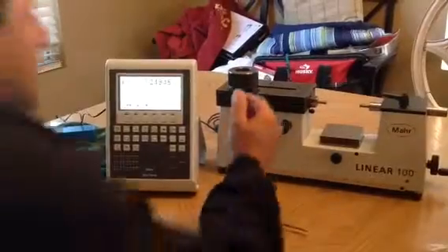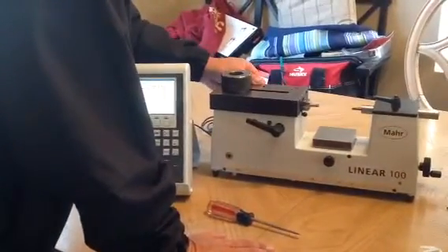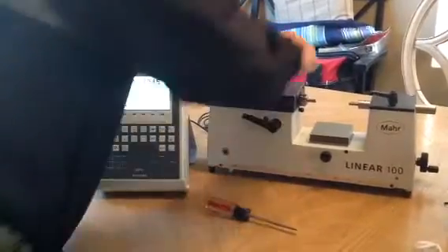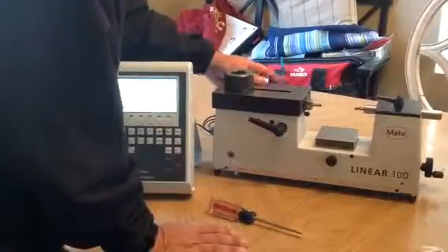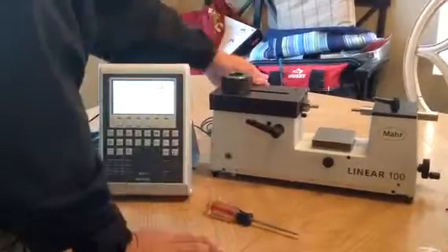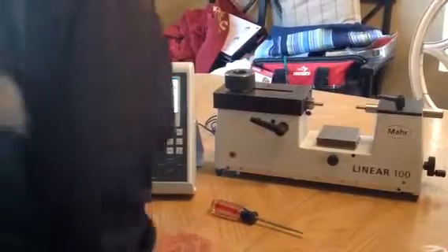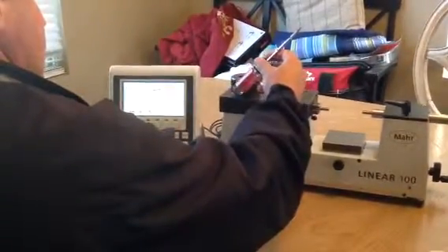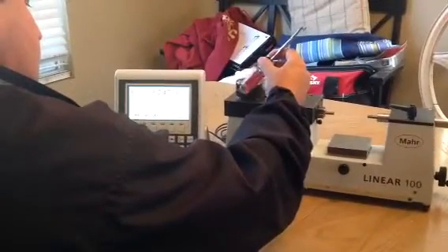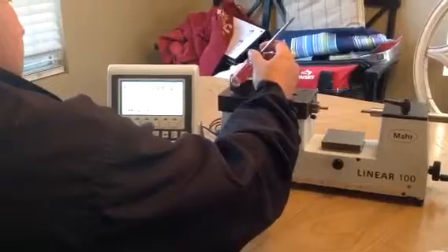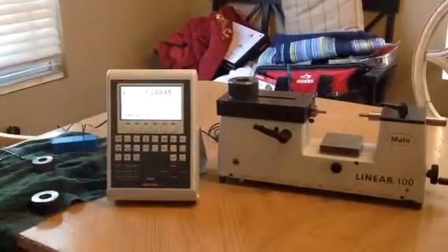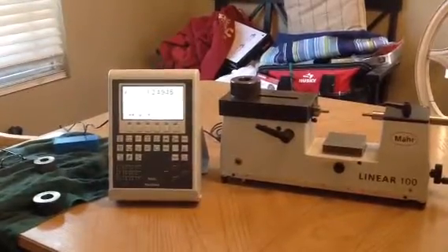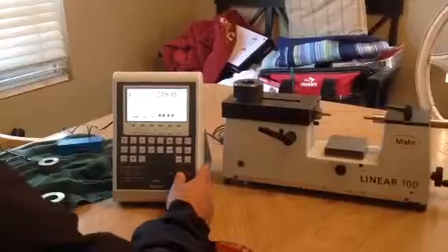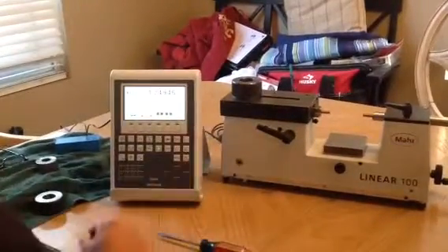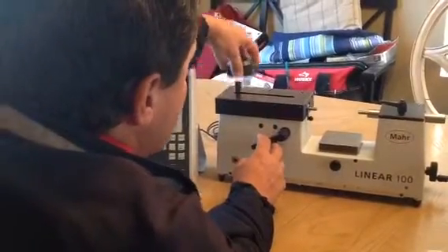And then, once again, you'll do top, middle, bottom to move it up and down. On the back of here, we have a winding button that will allow me to move the gauge up and down, the contact points up and down, right here. And then if I want to do it again, I just come here to my next spot, and I tap it. What it does, it locks on my max once again. So it's very, very simple to do. If I want to store that again, I hit store, it stores it. If I want to send it to the computer, I hit the data send to the computer. And that's how you do a ring.